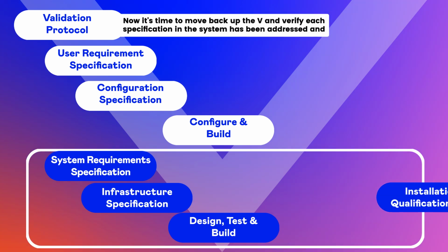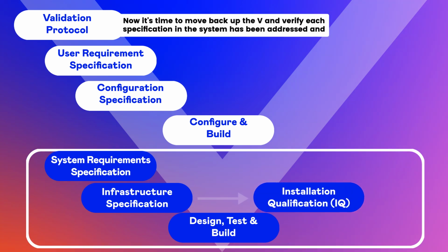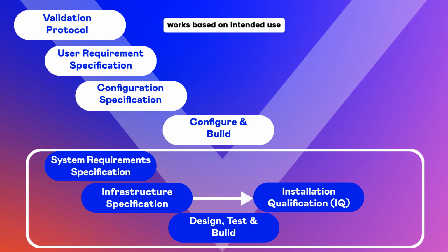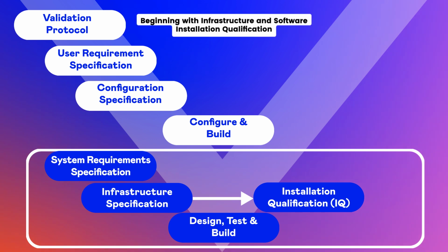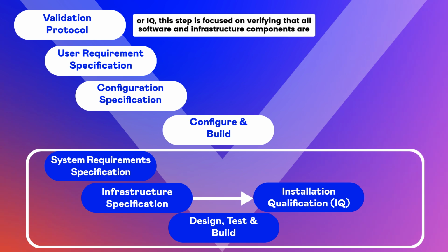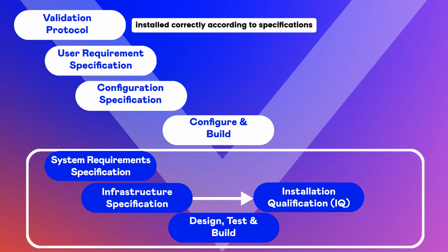Now it's time to move back up the V and verify each specification in the system has been addressed and works based on intended use, beginning with infrastructure and software installation qualification, or IQ. This step is focused on verifying that all software and infrastructure components are installed correctly according to specifications.